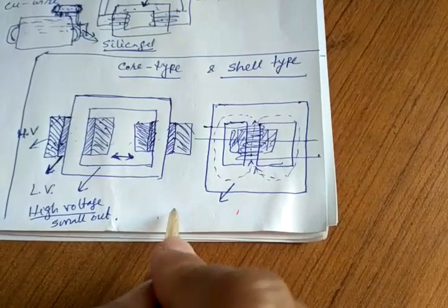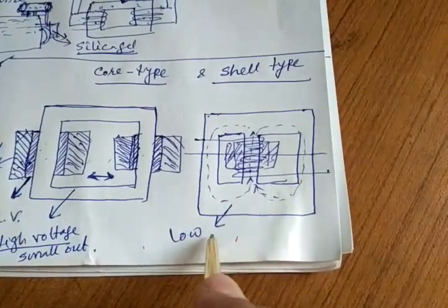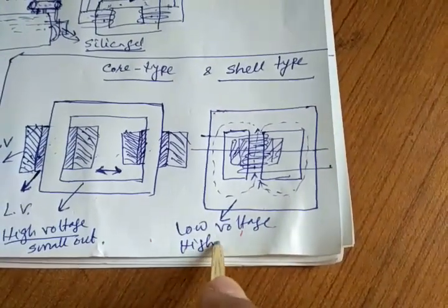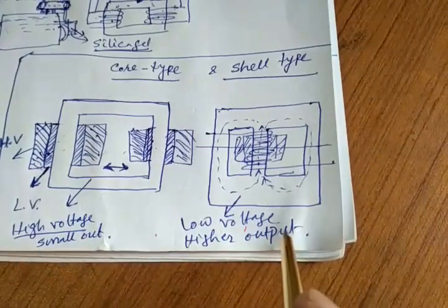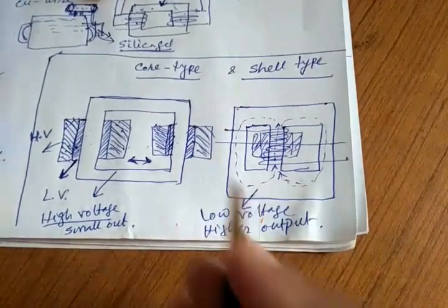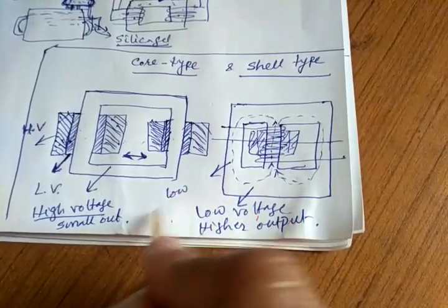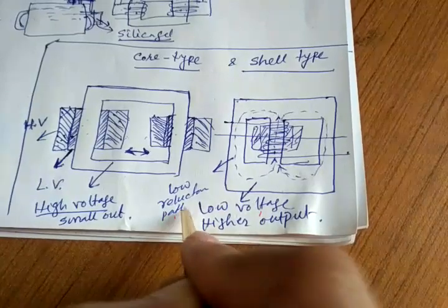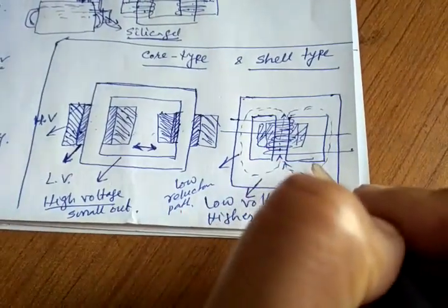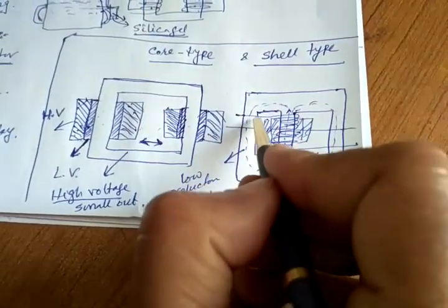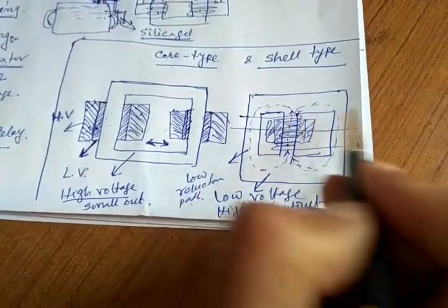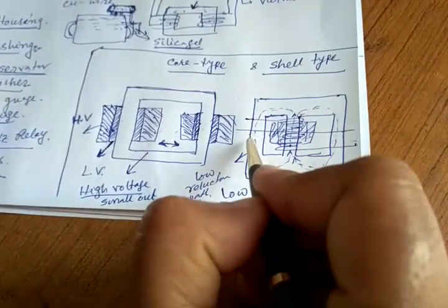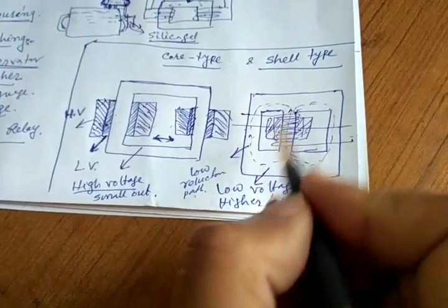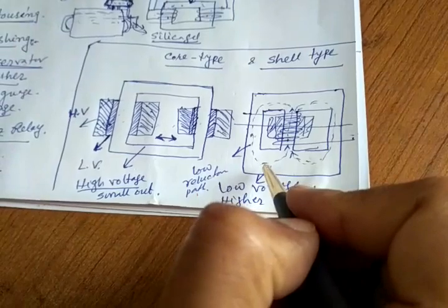And it is mainly used when the output voltage is low, low voltage but high output, higher output meaning higher kVA, okay, but low voltage. And this too provides a low reluctance path to the flux. So due to more core material, the flux leakage is less. And as the coil is surrounded from both sides, this is mechanically stronger, more robust, because the windings are covered from both sides by the core. This core is made of steel, so the windings are strongly encapsulated inside, and in that way it is more robust. But the one big problem of this is that the cooling is not good. Here due to this space, air cooling is possible, but in this case air cooling is not possible.